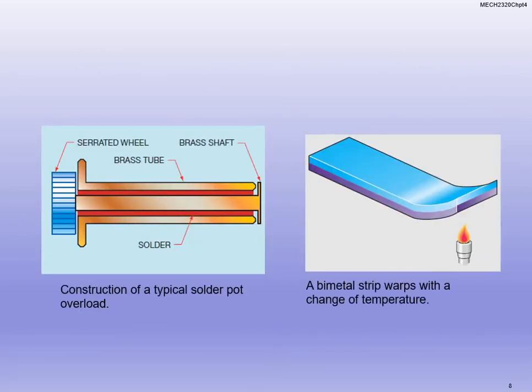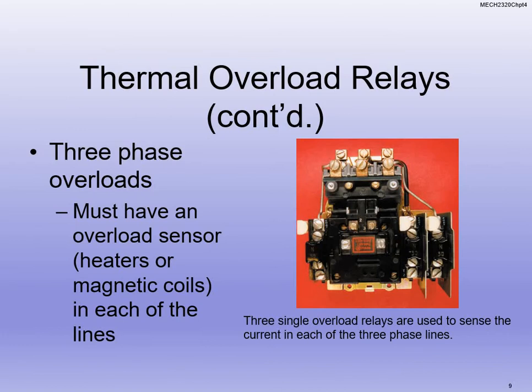So here's what's going on. If we look at a solder pot, it's kind of like what we talked about. We know that solder is sensitive to heat. If it's not hot enough, solder won't liquefy and it'll still hold it in place. Whereas if it gets too hot, the solder will liquefy, and then it'll allow that shaft to slide. If we're looking at the bimetal strip, if there's too much heat going through it, it begins to warp. When it warps, it opens the circuit up and the circuit trips. So that's how those work, just based on temperature.